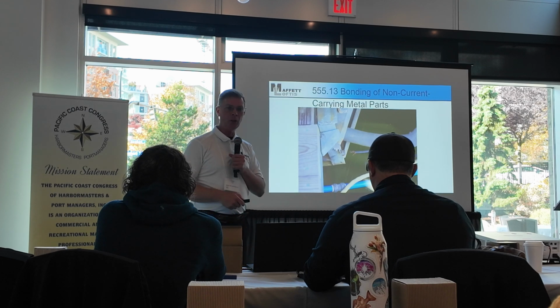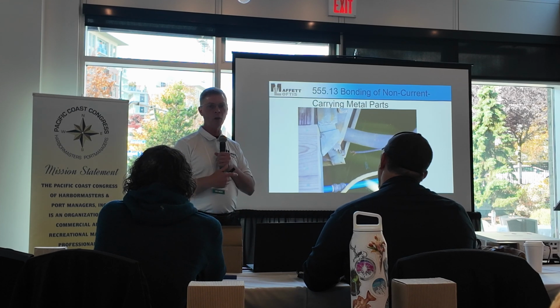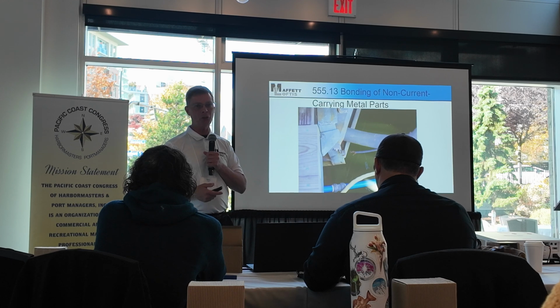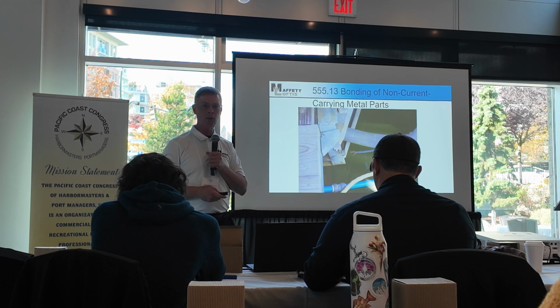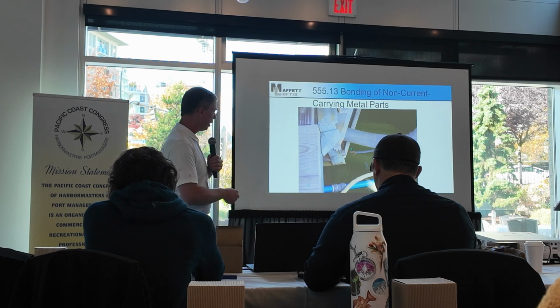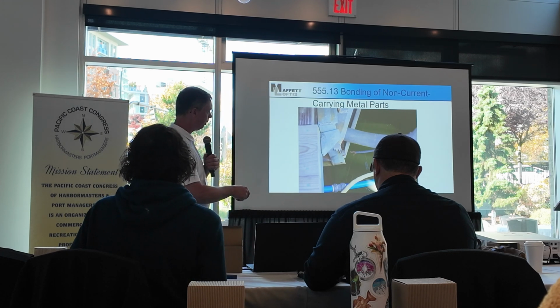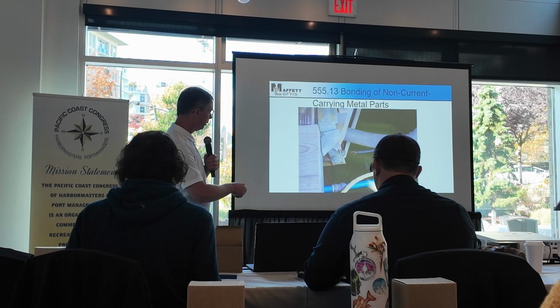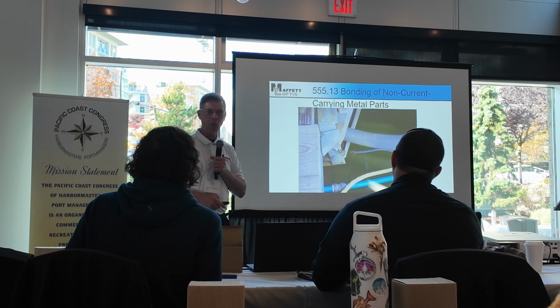You need to be looking at those bonding wires, because on just one dock I had probably six gangways, and all of them, the wire was disconnected from the movement of the dock. So that's your safety wire. It should be green, but in this case you can see the lug right there. It was once, at one time.